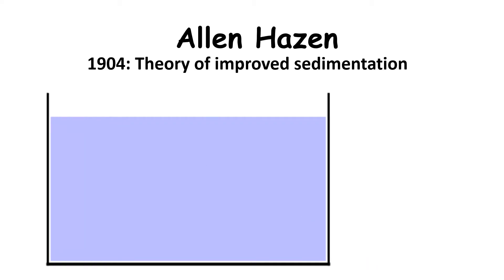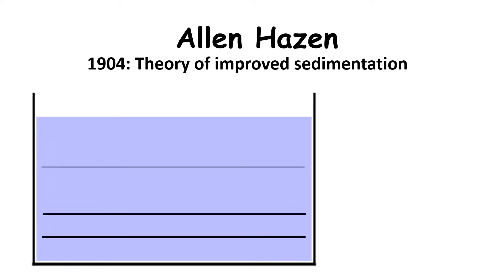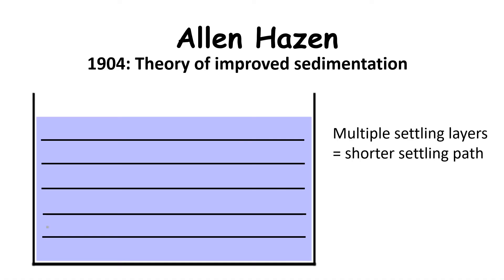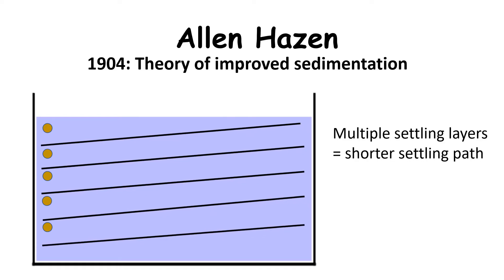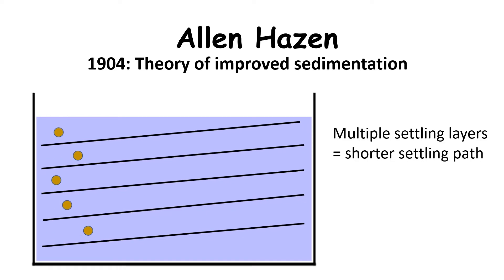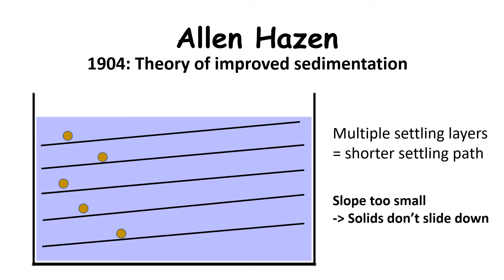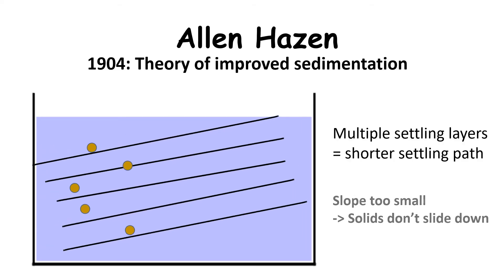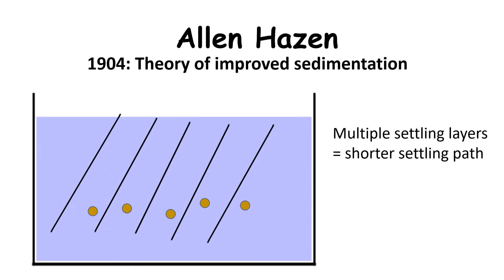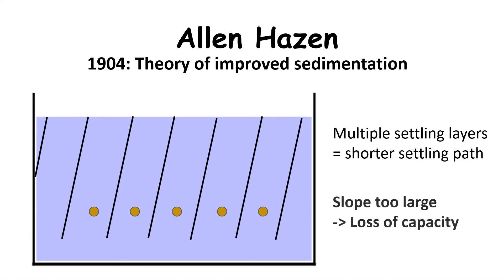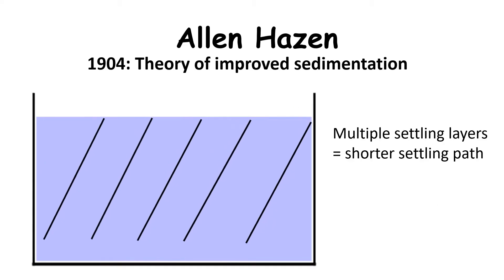To decrease the settling path of solids, multiple surface layers need to be added to the clarifier basin. To prevent solid build-up and clogging, the surface layers need to be inclined so that settled solids can slide down to the bottom of the basin and be carried out. If the layer slope is too small, solids won't slide down. However, if the layer slope is too large, the solid settling path is increased and less solids will settle out.